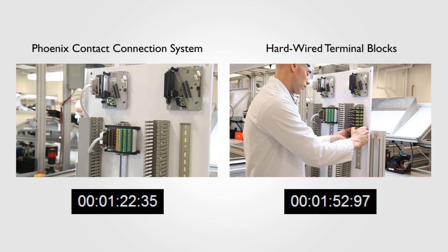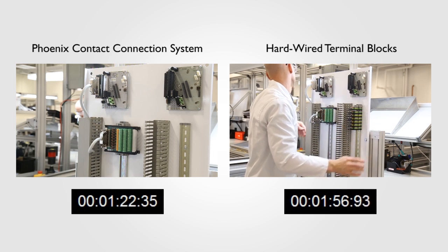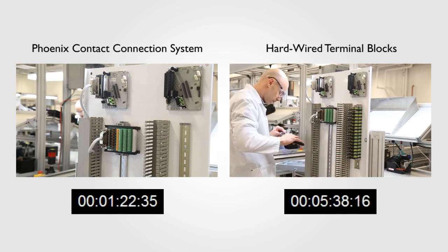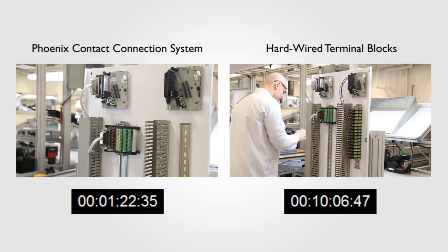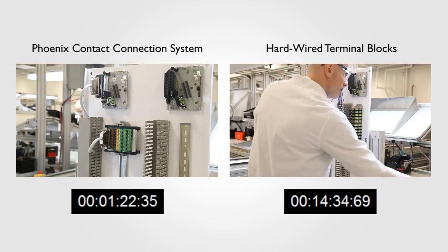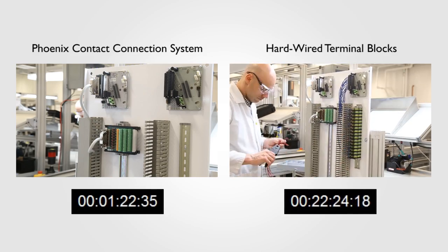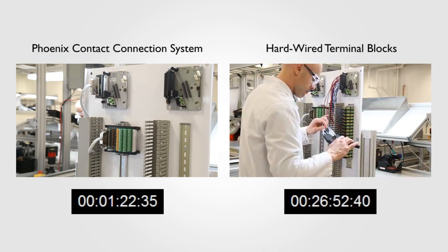But rather than make you sit through the entire installation, let's fast forward while keeping the clock in sync. So what exactly is taking place? Well, the measuring and cutting of all conductors, stripping, ferruling each end, and finally terminating each wire. And keep in mind, there are 48 wires — that means a total of 96 connection points, one for each side. Not only does that take a long time, it also gives you 96 potential points of failure in the system, and each will require additional testing before commissioning.